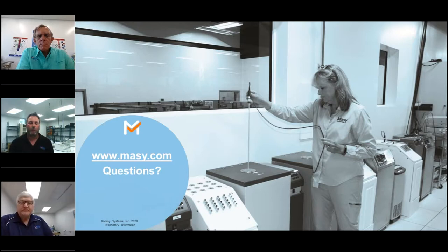That's a good question. I don't want to speak for other companies, but as an example, we have the ability to calibrate some of our own equipment. In this picture, one of our senior metrologists is working with our fixed point cells. The fixed point cells themselves get quantified at NIST, and we calibrate the SPRTs, so traceability goes back to NIST for the fixed point cells. Some cal houses can test or quantify certain primary standards internally. If not, they must use someone or something that can offer a good ratio, a good comparison between their best capabilities and what you're after.